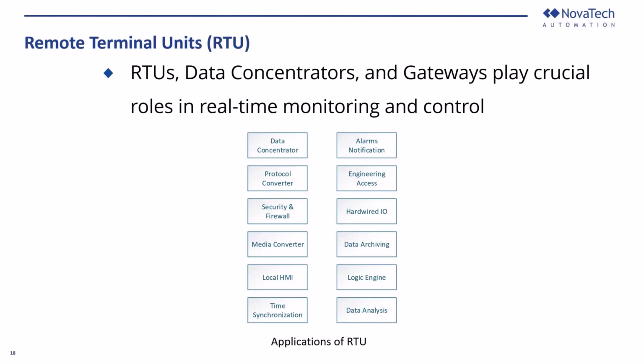Sometimes we also use the RTU as a media converter. For example, you have a physical media where the relays are talking serially, and you want to send fiber over to the SCADA system. So it converts serial to fiber, or serial to copper Ethernet. In an RTU, this typically means converting between electrical signals and optical signals, or vice versa, if that's what it's doing.